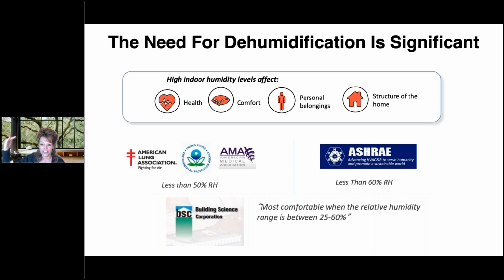The higher the temperature, usually the lower the RH, and the lower the temperature, the higher the RH. So that's when we get into really understanding what the dew point is, how much real moisture is in the air. But in wintertime, if we can keep it at around 25, which might mean in some parts of the country you're adding, but in the spring, summer, and fall, we really don't want to go above that 50% in our homes. And that's what Manual J has us designed for, is 50%.